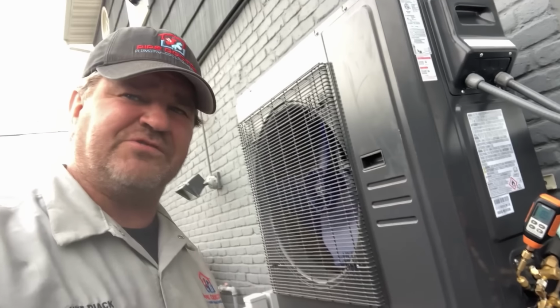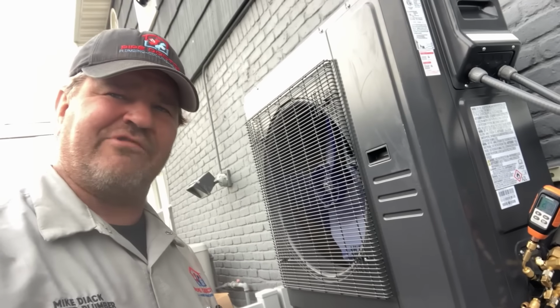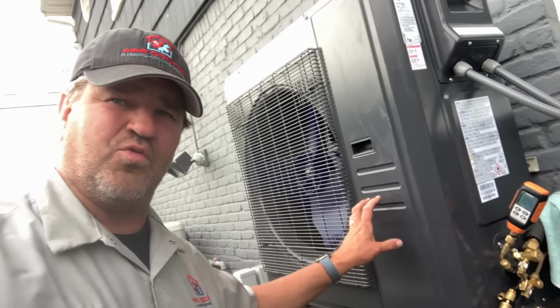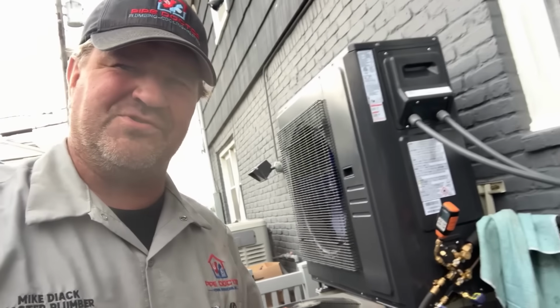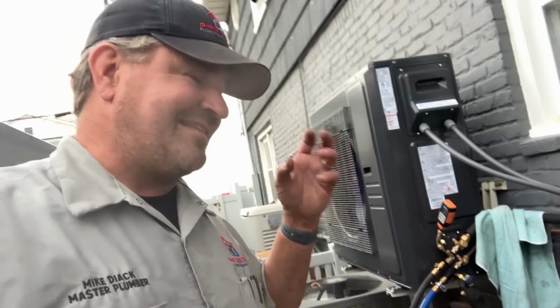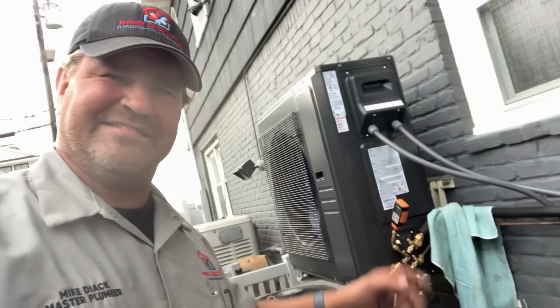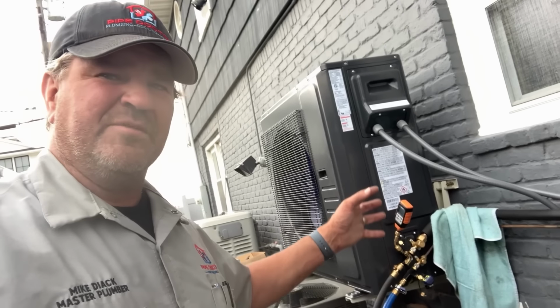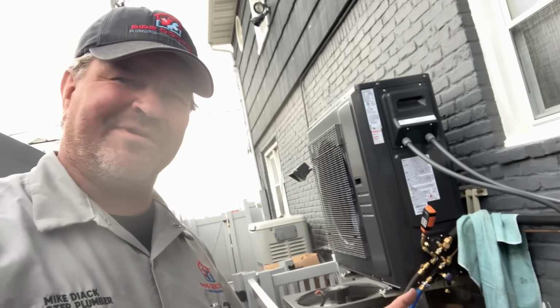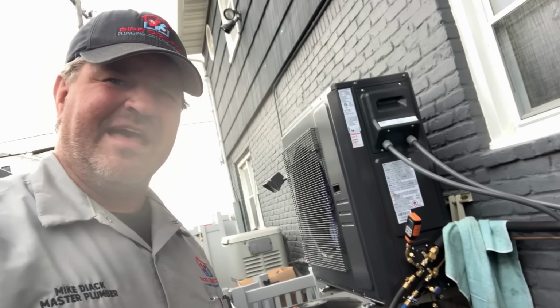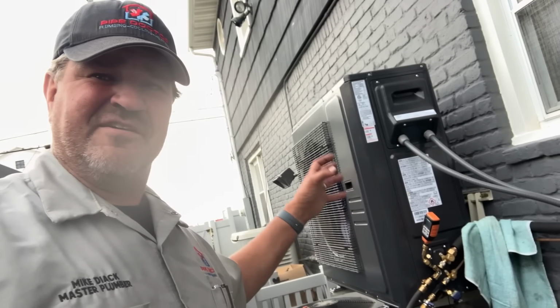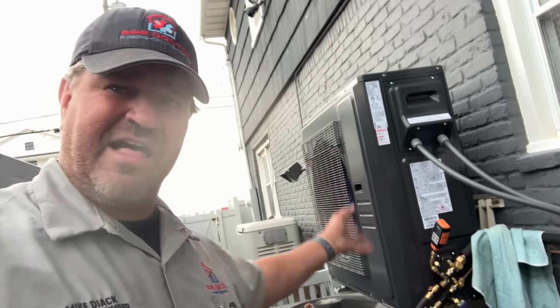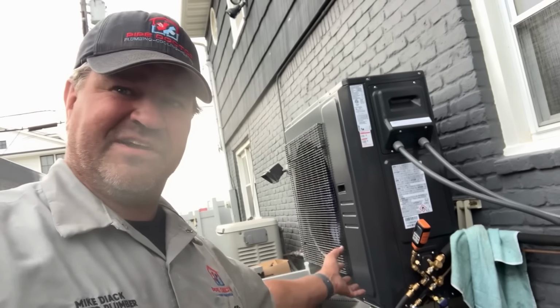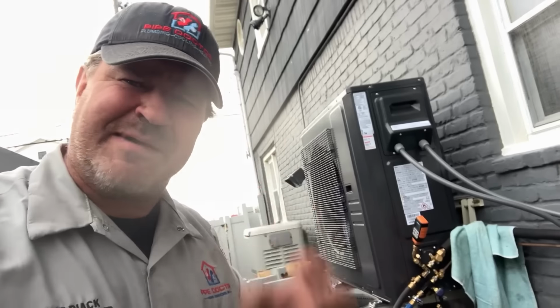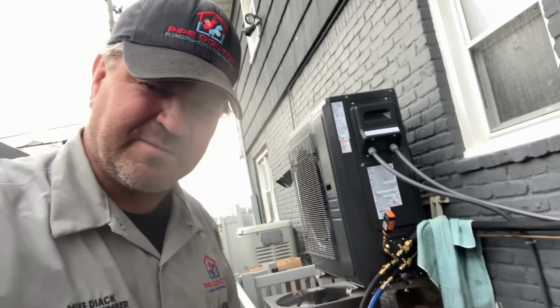That moisture can react with the refrigerant and the oil, creating acids that attack the compressor windings, bearings, and internal components. And over time, that leads to insulation breakdown, sludge formation, plugged expansion devices, poor performance, and eventually compressor failure. And that's when inverter compressors fail. You're not just replacing a $30 capacitor or an $800 compressor, right? You're replacing one of the most expensive components of the entire system.